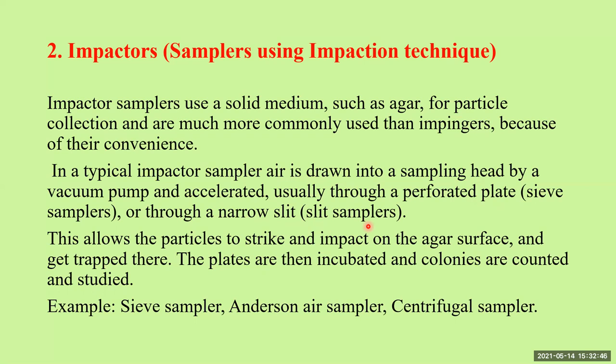Through the sieve sampler or slit sampler, a definite volume of air is accelerated and allowed to get deposited on the surface of a medium in a petri dish. This allows particles to strike and impact on the surface of agar, where they get trapped. The plates are then incubated, colonies are counted, and they can be studied. Examples include the sieve sampler, Anderson air sampler, and centrifugal sampler.